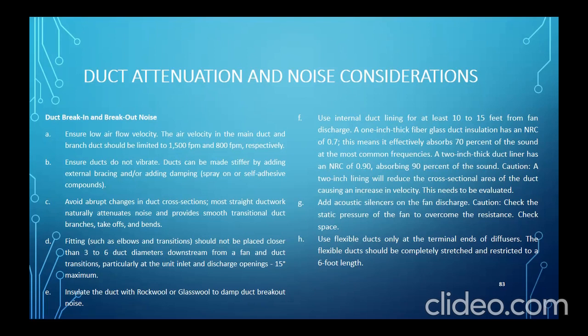Kasi normally, nag-uumpisang ingay sa fan. Sa may mga mataas ang NC niyan. So, lagyan mo ng acoustic lining. So, 2-inch thick duct lining has an NRC of 0.9, absorbing 90% of the sound. So, caution, a 2-inch lining will reduce the cross-sectional area of the duct, causing an increase in velocity. This needs to be evaluated.